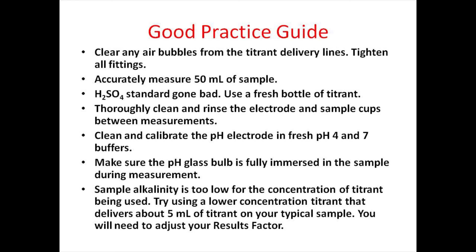An accurate titration should use between 0.5 mL and 10 mL of titrant. If you consistently use less than 0.5 mL of titrant, you may want to consider changing the concentration of titrant, which also requires changing your results factor. The procedure for changing your results factor is described in a second video. Keep in mind good laboratory practice guidelines by accurately measuring 50 mL of your sample, calibrating using fresh pH 4 and pH 7 buffers, and making sure the pH glass bulb is fully submerged into the sample for an analysis.